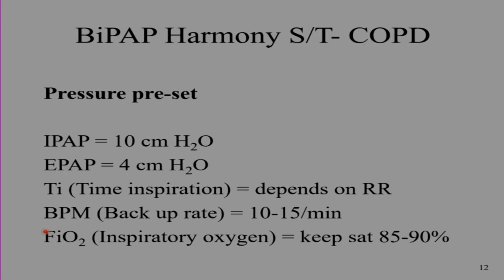Normally what we do is start the IPAP pressure around 10 centimeters of water, EPAP at 4 centimeters of water. As I said, IPAP will ventilate and EPAP will oxygenate. The inspiratory time depends on the respiratory rate of the patient, and is normally around 1 second or so. Set the backup rate around 10 breaths per minute, and for oxygen, target a saturation of 85 to 90%.